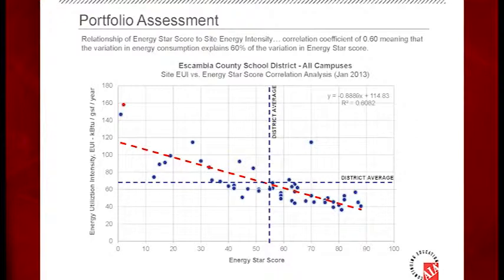The buildings up here, this 88 and all these, our second best building, we just tore it down. So what does that tell you? What do numbers on paper tell you? You know, the most efficient school possible is one where we turn all the air conditioners off and open the windows, and we have 15-foot candles on the floor, and we don't have any outside air, right? So numbers on paper aren't any good unless you're actually going out to see. That's the case with that building. It was slated for destruction, so they weren't putting any money into it. It didn't have outside air. It had window units. It didn't maintain temperatures. It looks like it's efficient, but it's not.